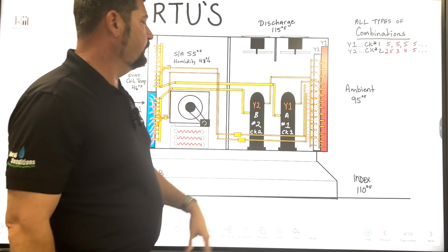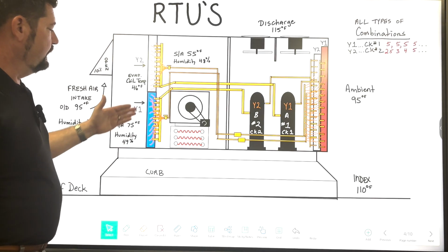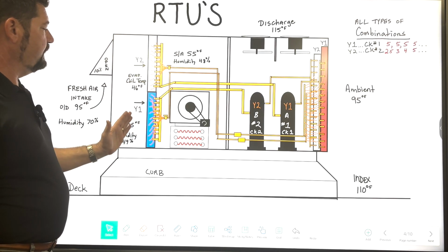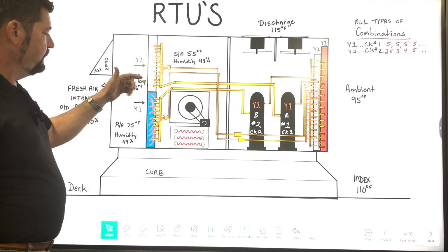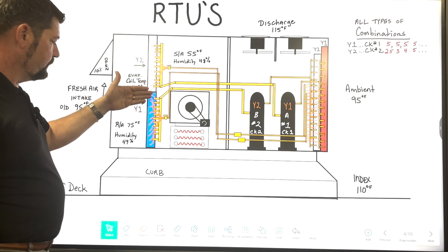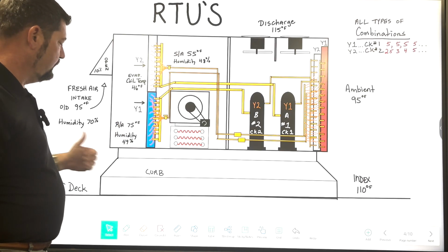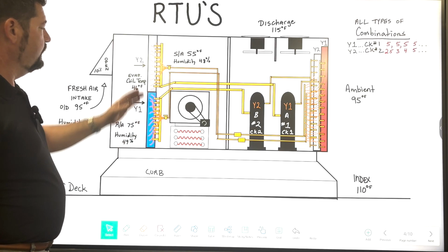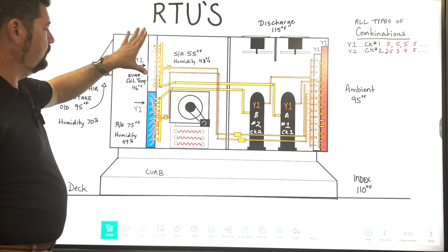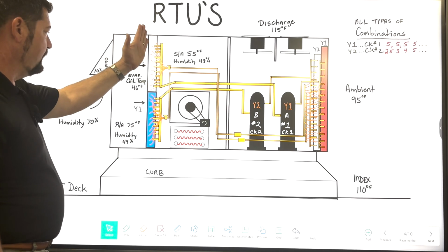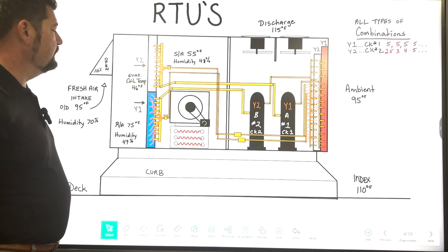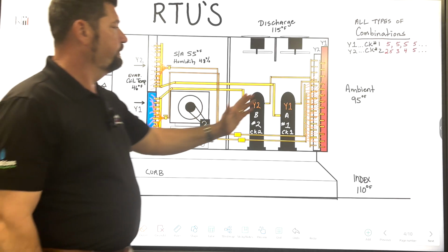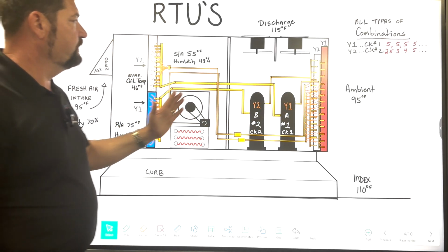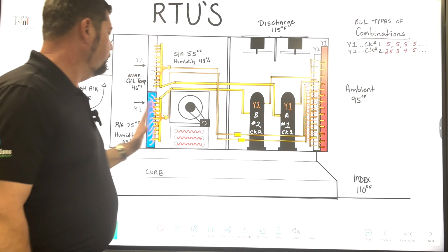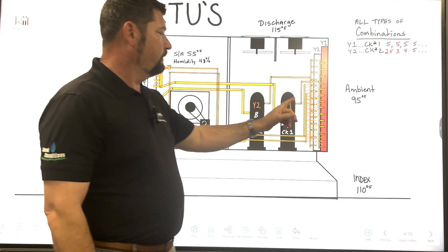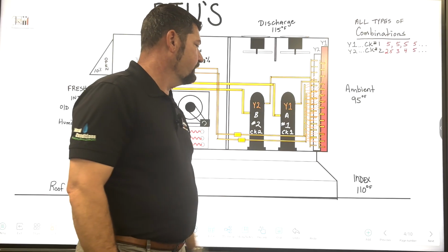Typically, it's the largest compressor, right? And this is going to be fine because you can't add humidity back into the building here, because the water is just running into the drain pan and out the actual RTU. Whereas the way we had it before, the Y2, if it was running and the Y1 was not running, then that water would roll down and pull back in. So this is the way that the equipment should stage. It should stage in Y1 first, which would be the bottom of the coil. Doesn't matter which one of these is Y1, I just drew it out this way.